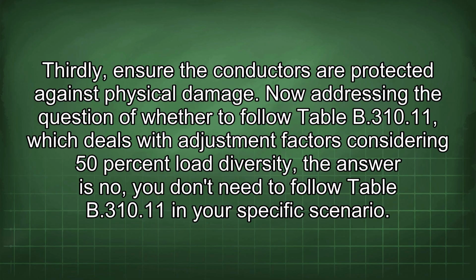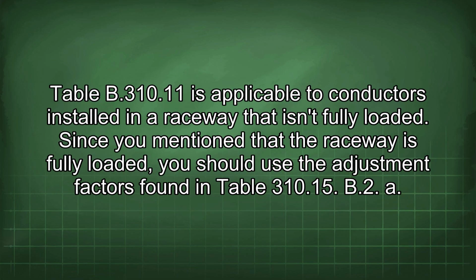Now addressing the question of whether to follow Table B 310.11, which deals with adjustment factors considering 50% load diversity, the answer is no, you don't need to follow Table B 310.11 in your specific scenario. Table B 310.11 is applicable to conductors installed in a raceway that isn't fully loaded. Since you mentioned that the raceway is fully loaded, you should use the adjustment factors found in Table 310.15.